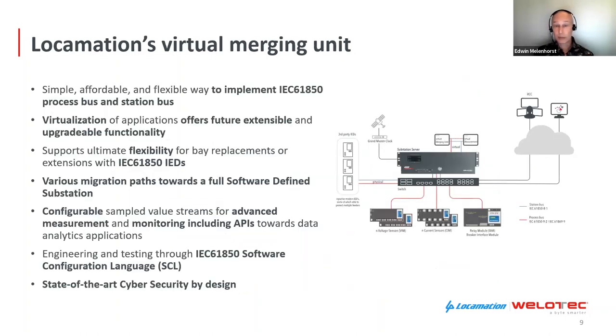So in short, we have a relatively simple, cost-effective, and flexible way to implement the IEC 61850 process bus and station bus in existing substations. In the future, the virtualization of substation functions offers extensible and upgradable functionality. It supports ultimate flexibility for bay replacements or extensions with third-party IEC 61850 IEDs, and various migration paths towards a full software-defined substation. It's up to the DSO or TSO in which way they want to build, refurbish, or extend their substations.